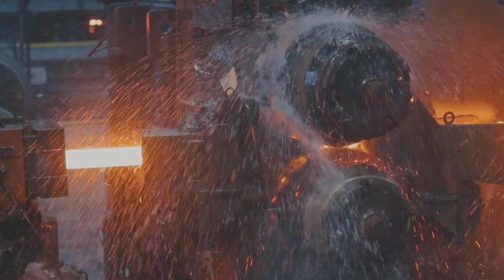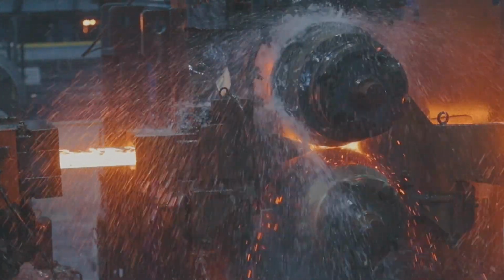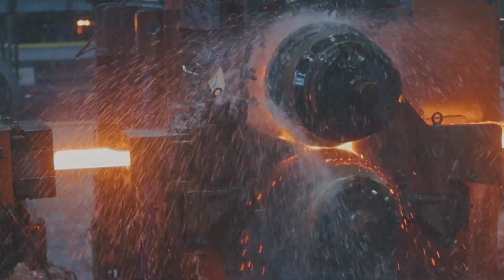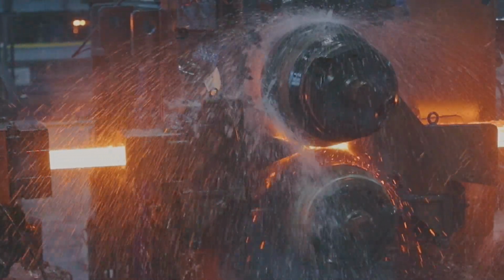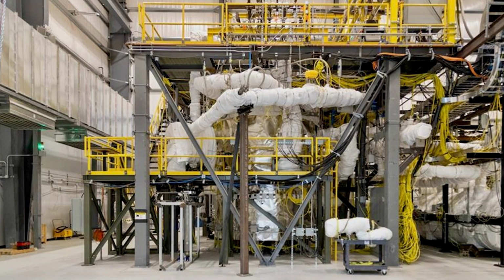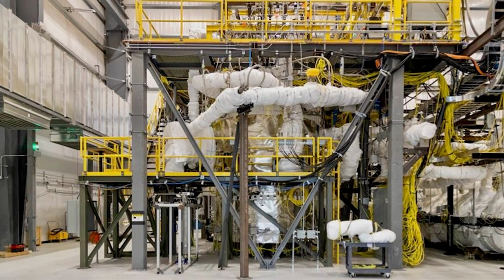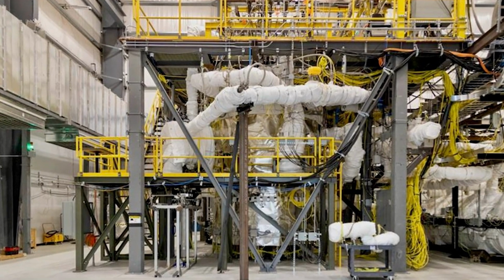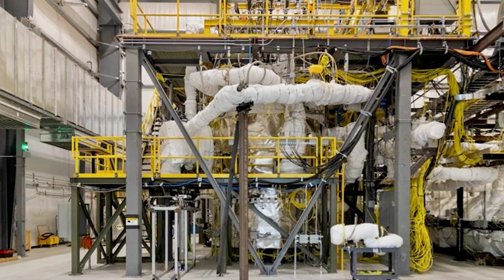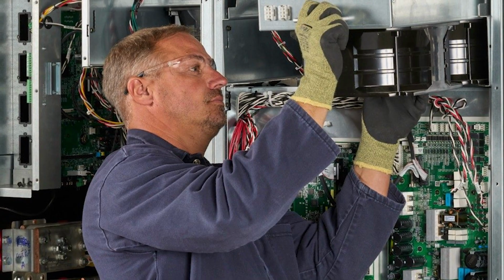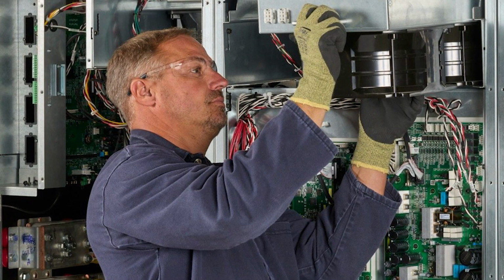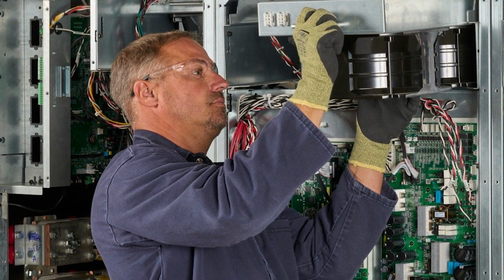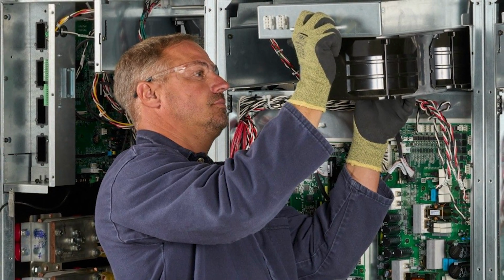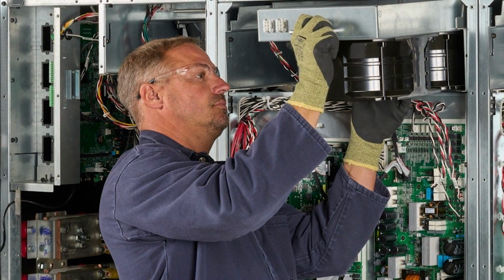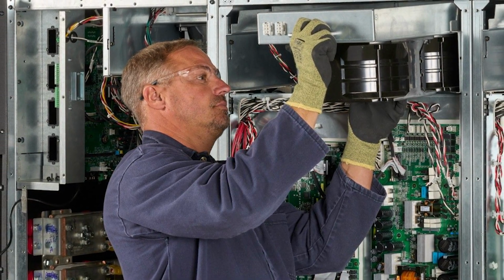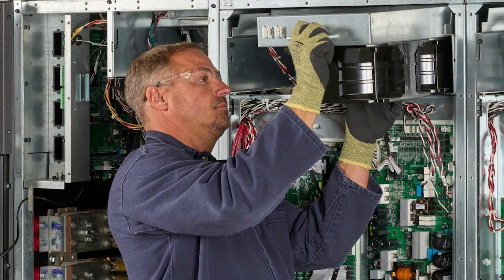You've got a critical process where something will be damaged, or you've got molten metals or something in a line, or molten salts or anything, that if the power goes out and it sets in that pipe, you have to replace all that pipe. It should be, first and foremost, put a UPS on it, so that when the power goes out, you can get a signal saying, hey, the power's out, I've only got so much time. You can shut down the process line, allow the pipes to be evacuated so that nothing sets in the pipes.